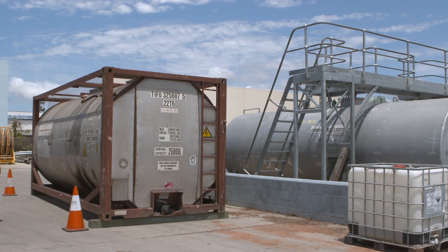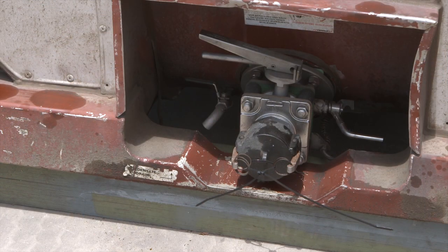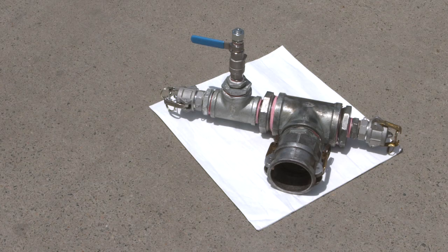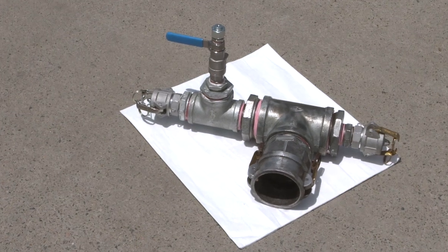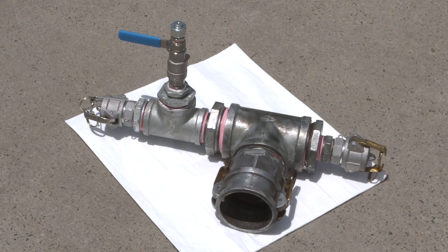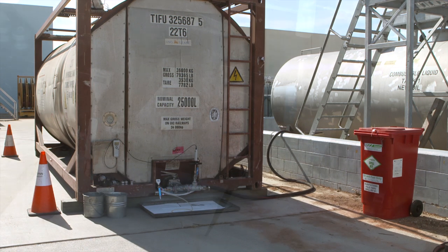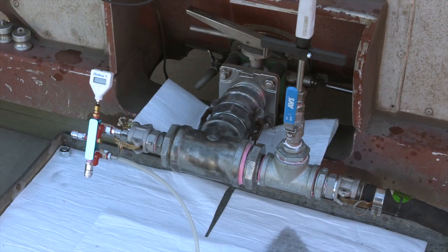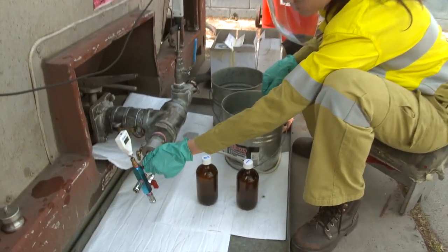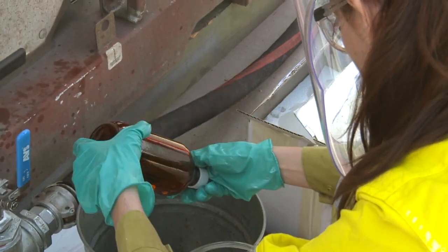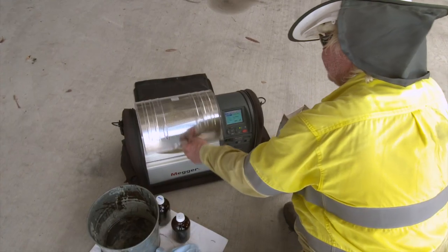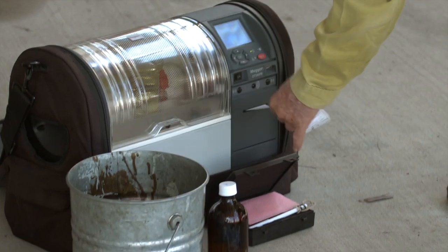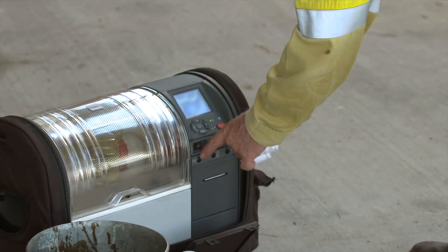Once the oil arrives from the supplier, it is important to make sure all the taps are turned off so there is no spillage. The next step is to screw in your adapters. Depending on what type of tanker you get, you may need different fittings for your manifold. After the adapters have been fitted, you are then right to take your sample, remembering to clean your bottles before you take the sample. Once the sample has been tested and passed, you are then able to fill up your bulk storage.